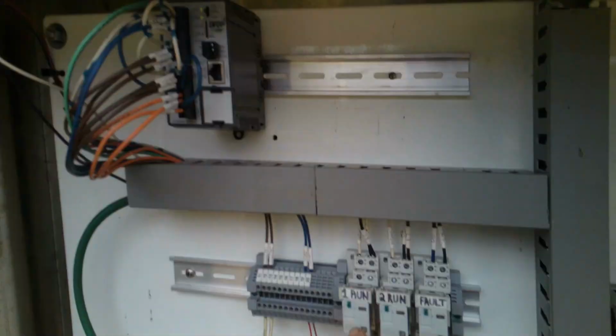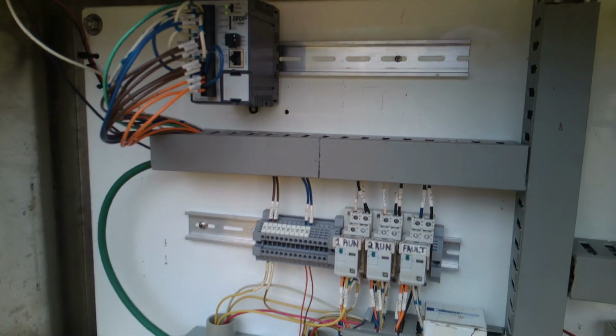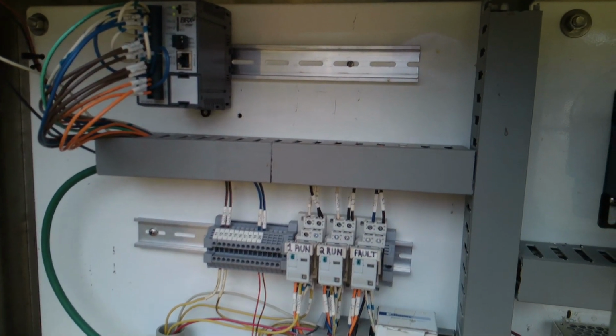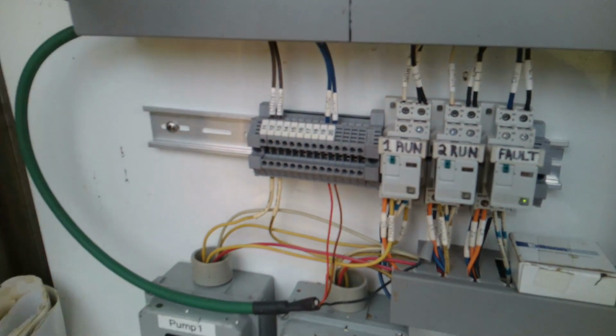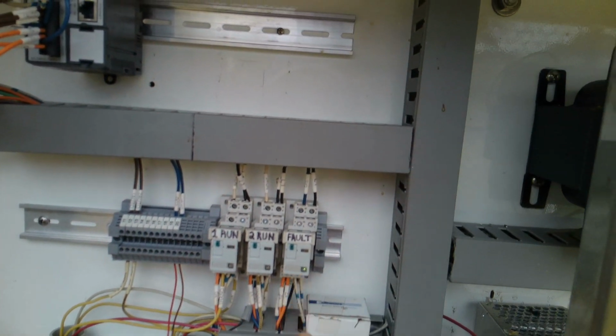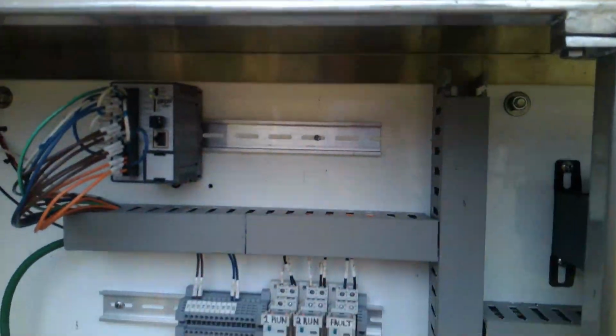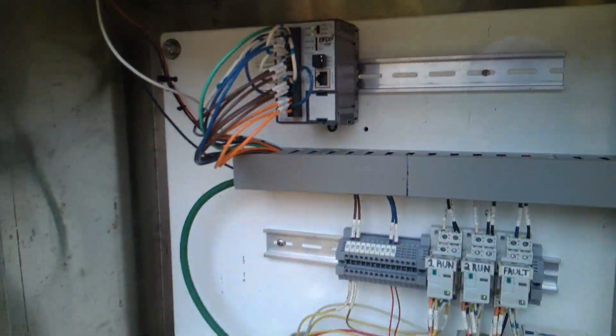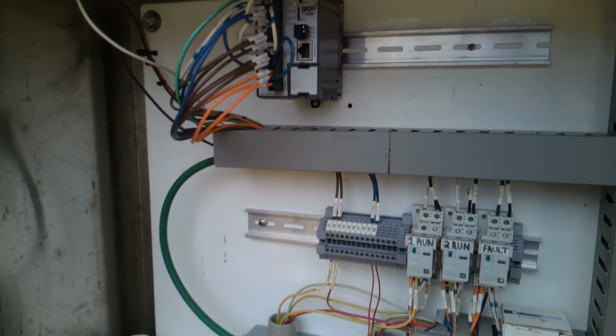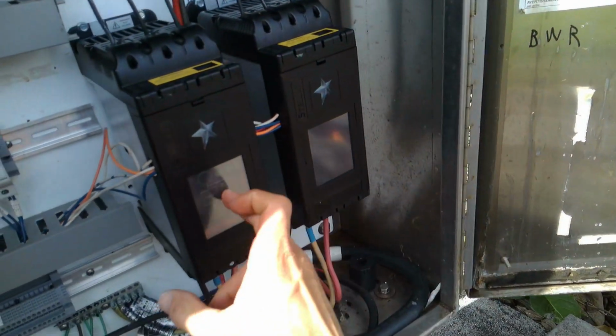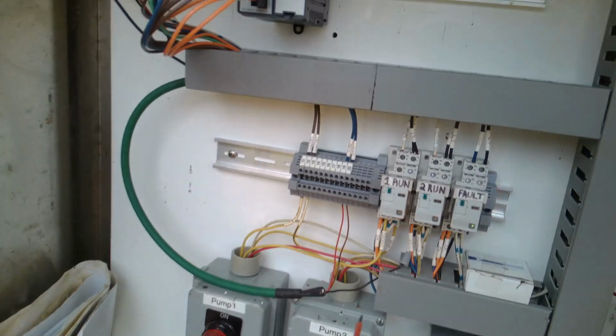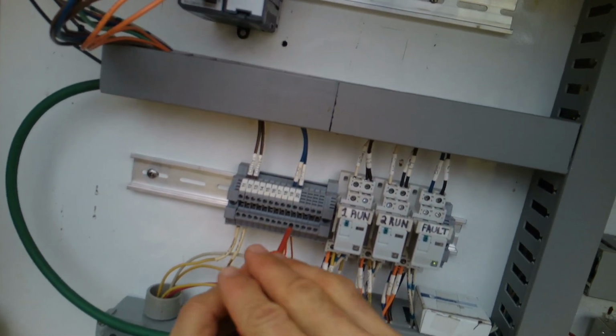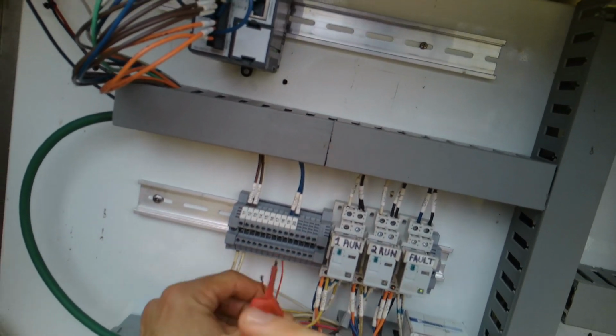Look at that. It's definitely jittering. That's a gecko. Oh, look at that. Look at these outputs faltering, faults coming true. That is bad. That is not good. Let's try removing the transducer, see if the problem goes away.